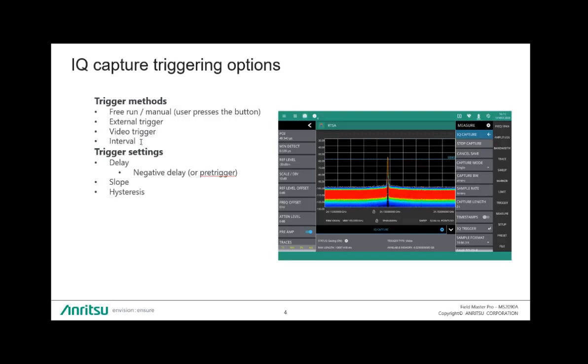You can also set intervals. So if you wanted to do your capturing once an hour, once every five minutes, every ten minutes, you can set that interval, and it will automatically make those captures for you. We also offer a trigger delay, and what's nice here is we offer a negative trigger delay, which is the same as a pre-trigger. So essentially, if you have a signal that you want to capture for 100 milliseconds, but you want to know what happened in the 10 milliseconds before that, then you could set your capture time to 110 milliseconds with a negative 10 millisecond delay, and that will capture that 10 milliseconds before the trigger actually happens.